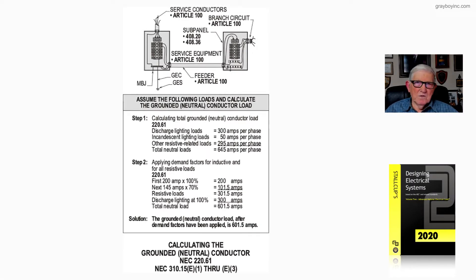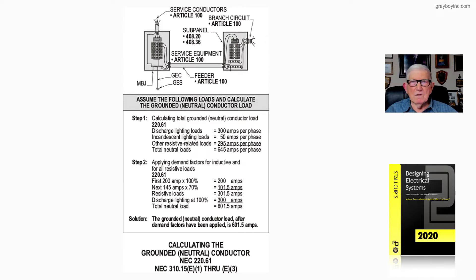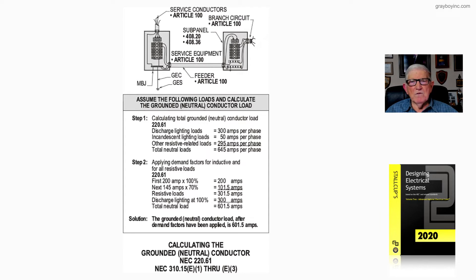Now let's take a look at figure 23-21. We're dealing with calculating the grounded neutral conductor in accordance with 220.61. Before we get into the calculation, let's take a look at the service conductors defined in Article 100, but all the requirements for the service conductors are in Article 230.